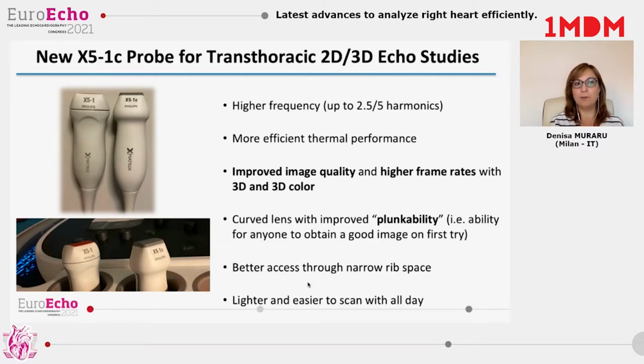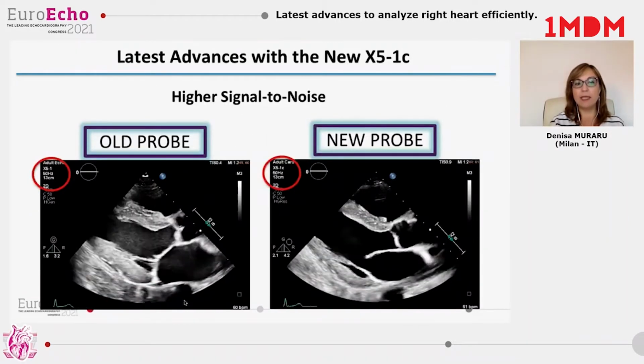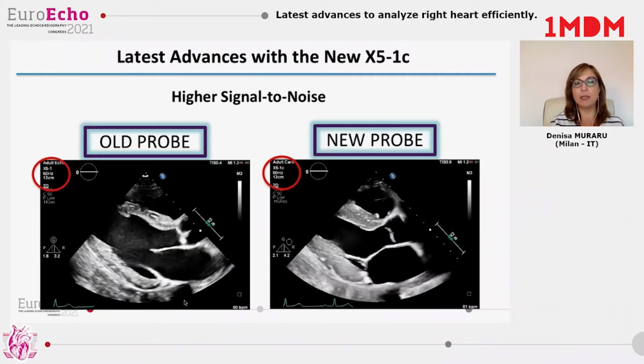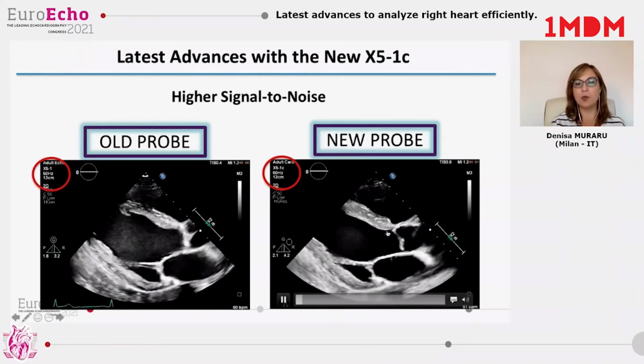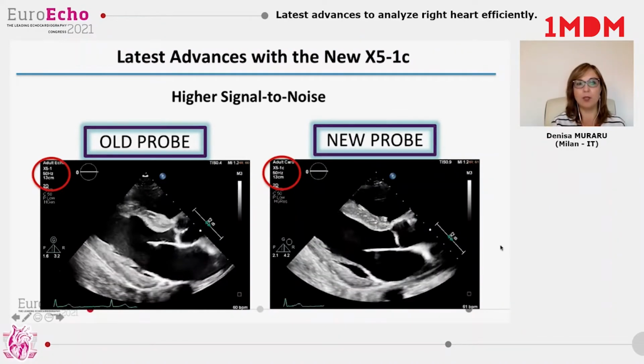and 3D color. The transducer also has a curved lens, as you can see from this image, that allows better access through narrow rib spaces, and has improved scanability, which means a greater ability for anyone to obtain a good image on a first try, and also a faster examination. Finally, this new transducer is lighter than the previous one, easier to scan all day, and has increased durability. What does it mean practically? It means a higher signal-to-noise ratio, greater ability to detect small signals, for instance, to image the thin aortic valve in a normal subject.